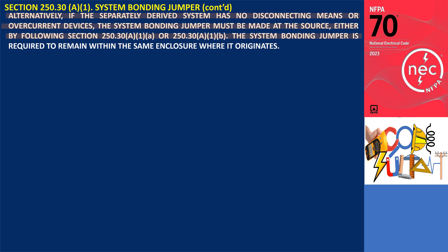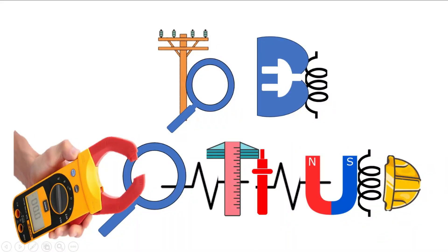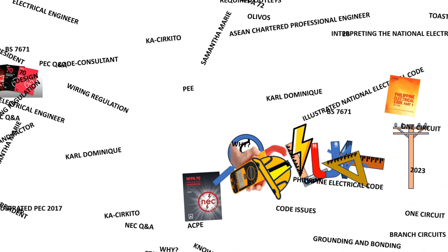The system bonding jumper is required to remain within the same enclosure where it originates. However, if the source of the separately derived system is located outside the building or structure being supplied, a system bonding jumper must be installed at the grounding electrode connection, as per section 250.30 C. Thank you all for watching.